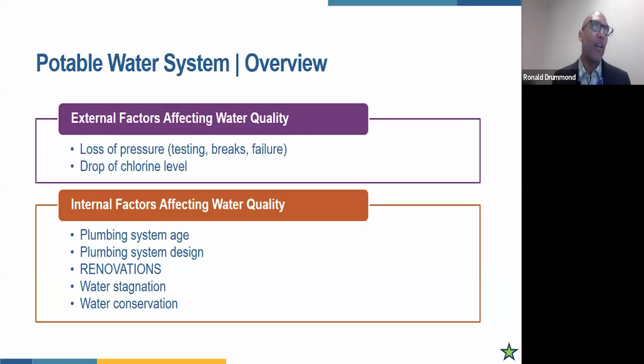Oftentimes, I know for us at the Ottawa Hospital, the city does test its pressure a couple times a year. And during those times, we can see drops in pressure that could raise some of that bacteria getting into our potable water supply. So we have to watch out for that. There could also be failures outside of the building, main breaks, etc., that will lead to contamination of your potable water supply. If you have a main break outside your building, you're likely going to have to do a hyperchlorination exercise once that water is turned back on, regardless of whether you have Legionella or not.